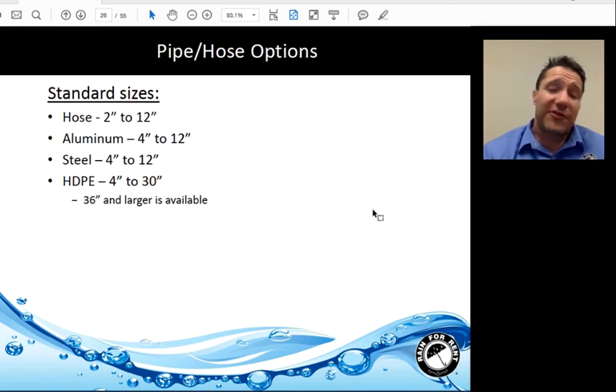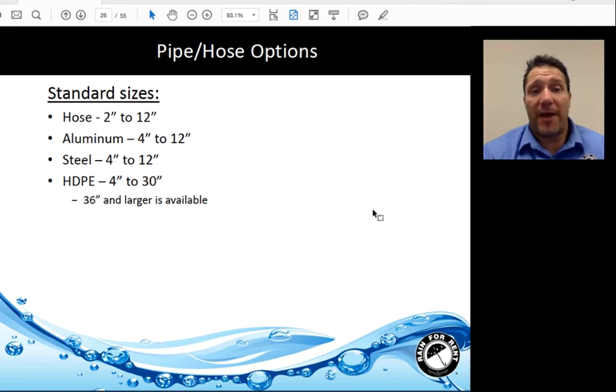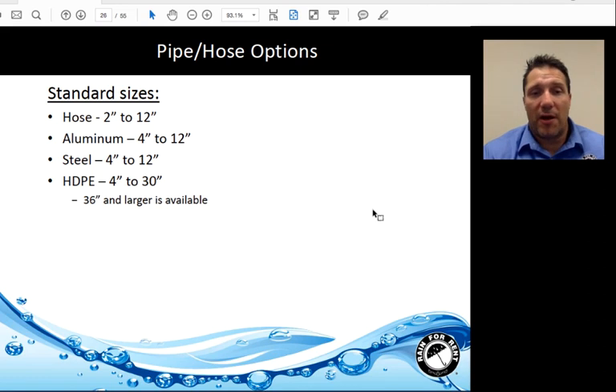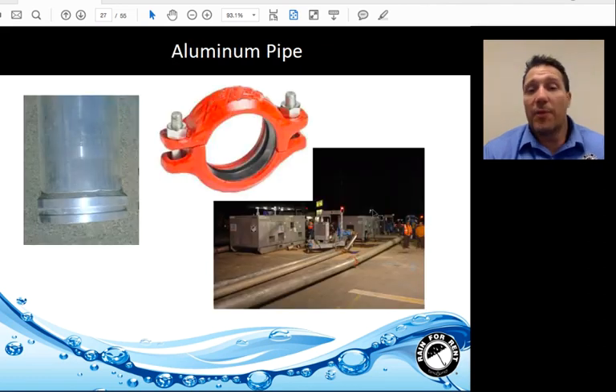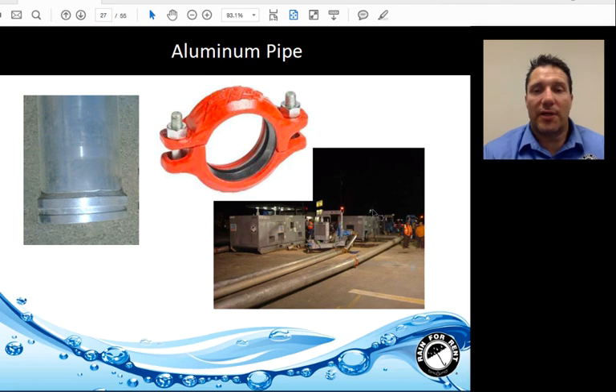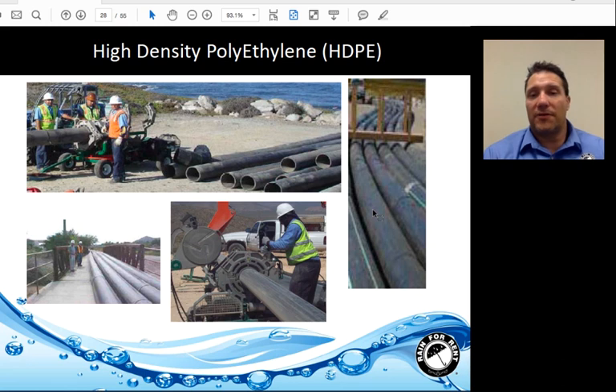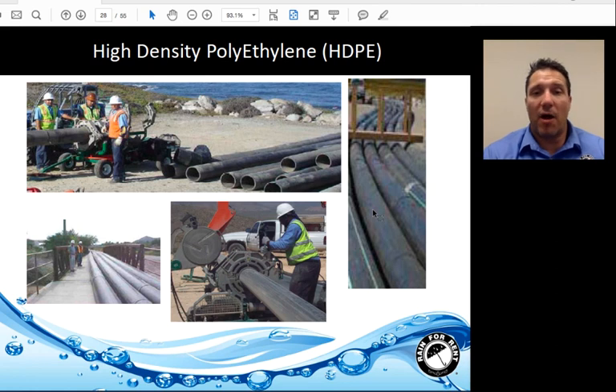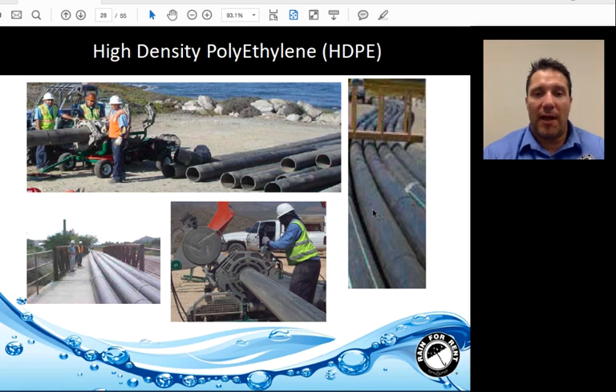Pipe and hose selection: Standard-sized hoses in most rental fleets run from 2 inches to 12 inches. Rain for Rent standard aluminum pipe comes in 4 to 12 inches, and we also have 4 to 12 inches steel pipe. HDPE ranges from 4 to 30 inches, with 36-inch and larger sizes also available in the rental fleet. Aluminum pipe is a self-restrained, zero-leak connection — very light, handles high pressure, and is quickly installed. HDPE is very durable, uses a fused connection process, so once fused correctly it's essentially one long piece of pipe, and is chemically inert.